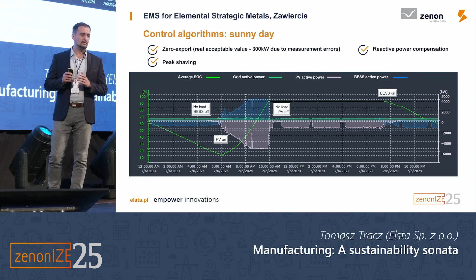And the main factor for this project was energy cost management, because it's all about return of investment. And here I would like to present two simple slides which we've made. One is for a sunny day, the next one will be for the worst condition. And like I said, it was zero export, but when we calculated the values of the current transformers of the analyzers, we checked the error - it summed up to 300 kilowatts, which can occur due to measurement error.